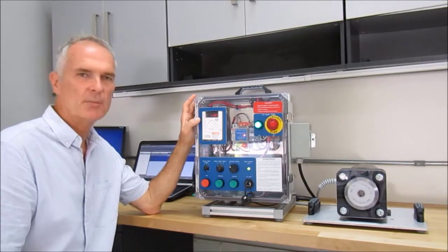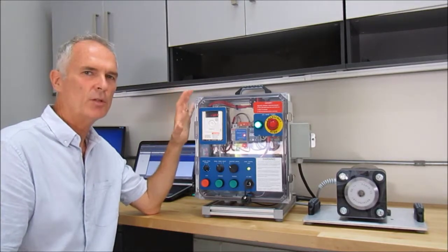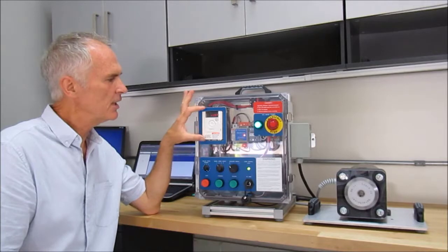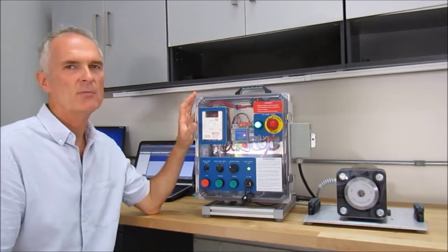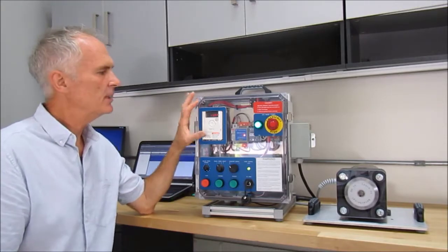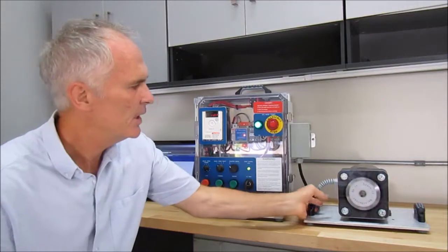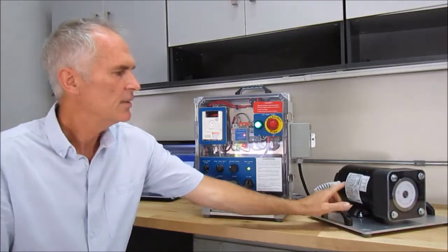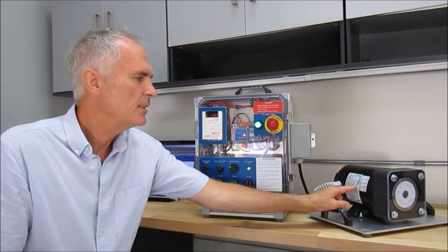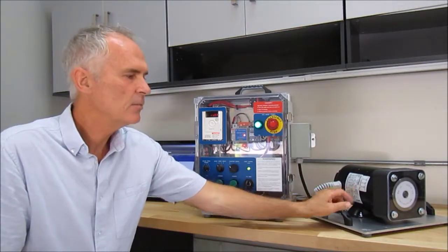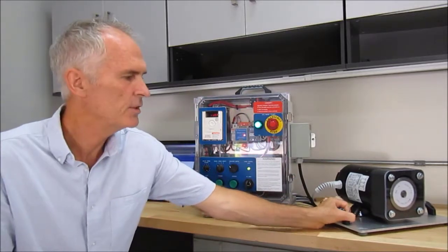We're going to talk about a couple of different things in this video. We're going to talk about motor parameters and running the drive in local mode. Okay? Motor parameters are probably one of the most important parameters that you will enter into the actual drive. Okay? You need to look at the motor nameplate and you need to get the voltage, the frequency, the current, the RPM. Possibly it may ask you for the power factor of the motor. You need to take that information and you need to enter it into the drive before you do anything.